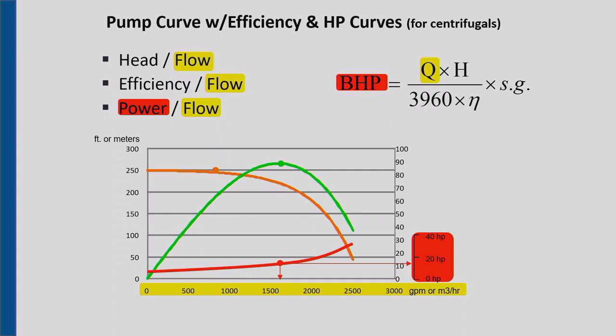And then I've got power. The formula up here says, hey, if I have flow and I have head and I have efficiency, I can multiply this whole side out and I can get power. Right? So for any point on the curve, I got head, I got flow, I got efficiency, I have power. I got a power curve down here. Okay? Interesting thing about the power curve. You'll notice that as the flow goes up, the power goes up.